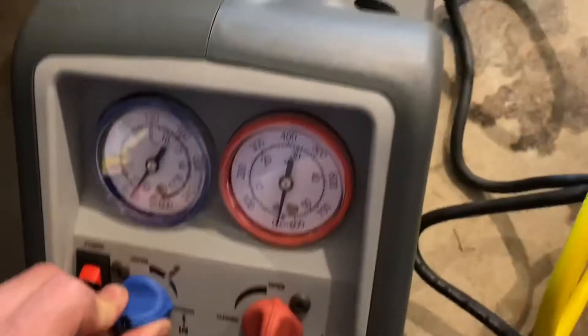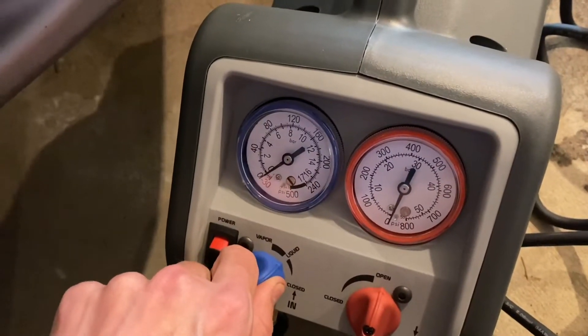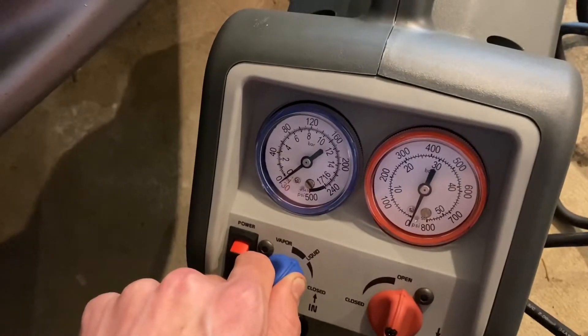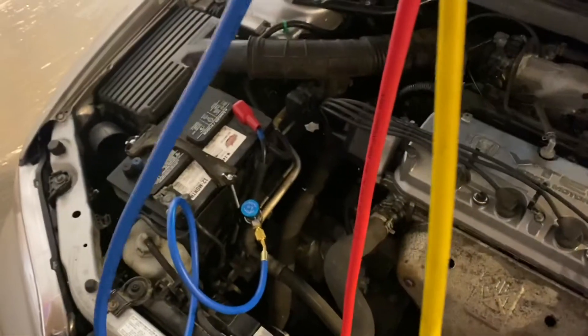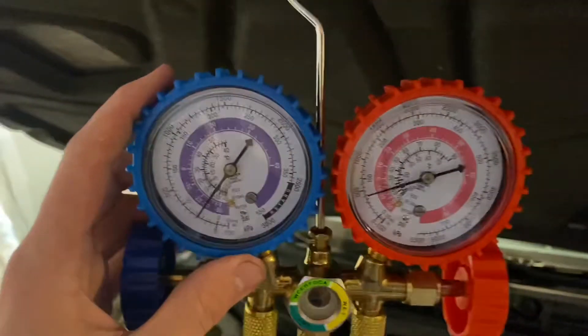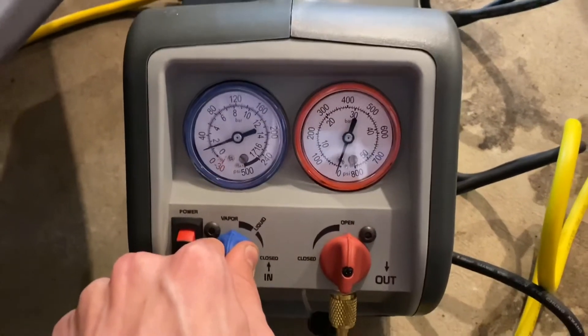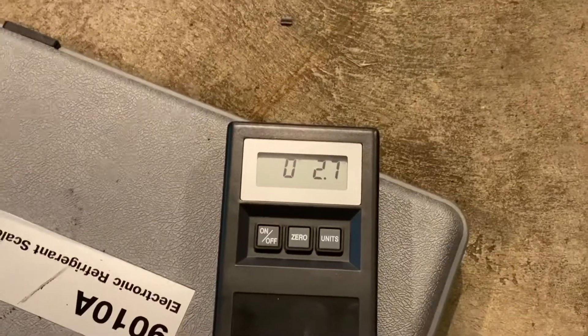We're going to flip this on, and you can hear that going. That wasn't open enough, but now we've got that screwed down more, we've got pressure here, and that's going to start to pull the pressure into this unit and into the tank. You can hear it whooshing in there, and you'll see the amount of refrigerant on the scale start to creep up.